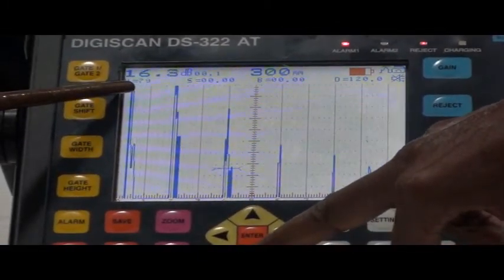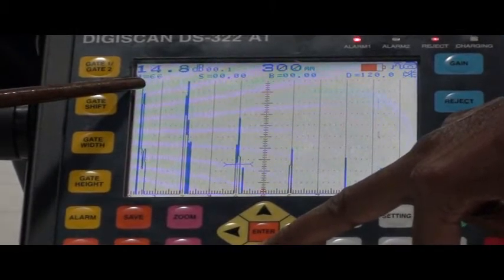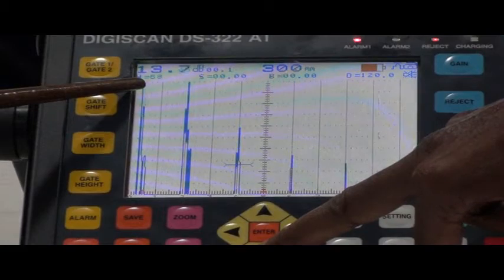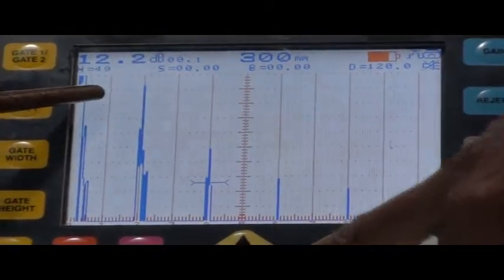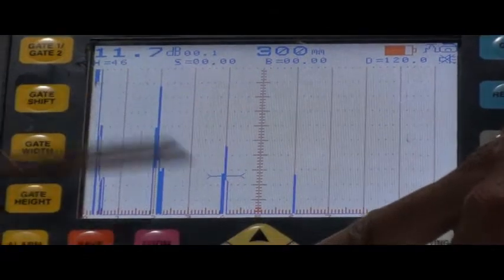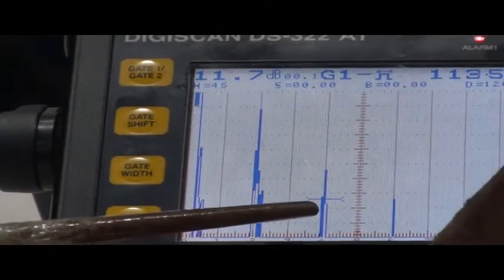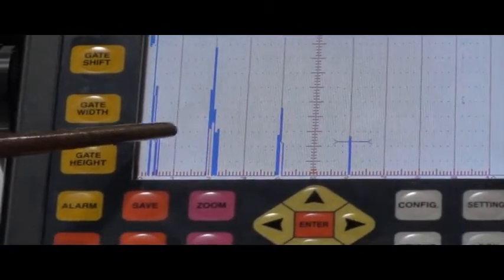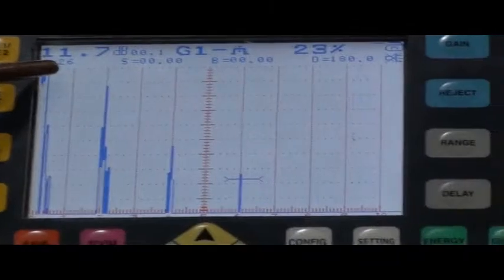It reduces to 45. Previously it was 90, so now we have made it half — it is 45. We then read the amplitude of the n+1 echo. It is 26. So H2 is 26.